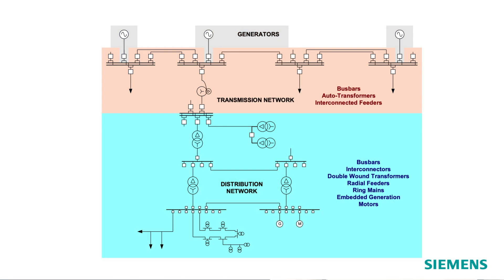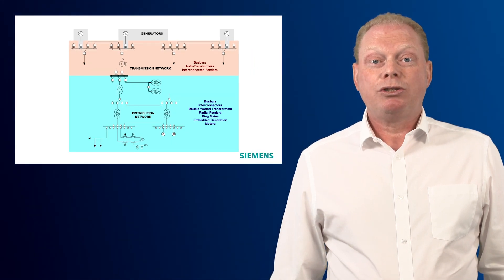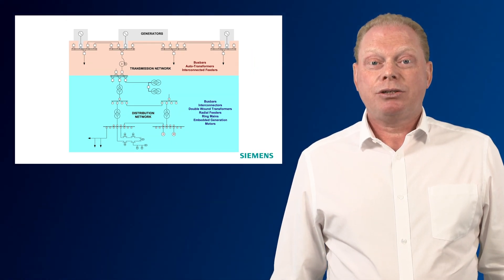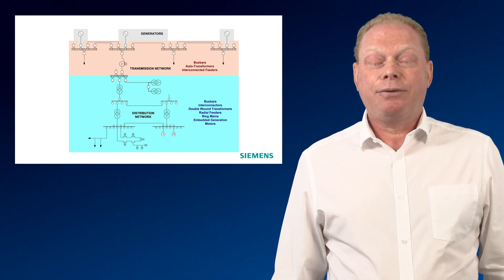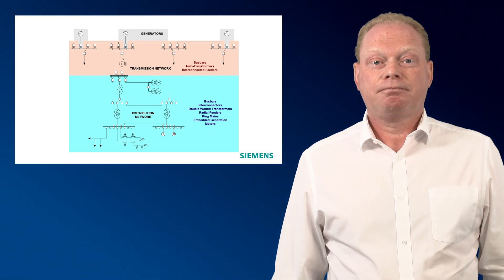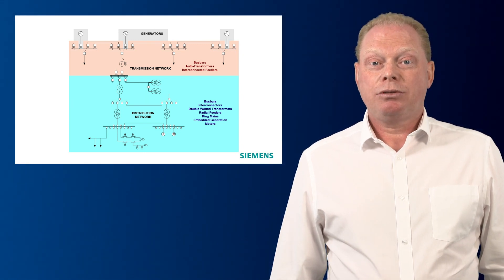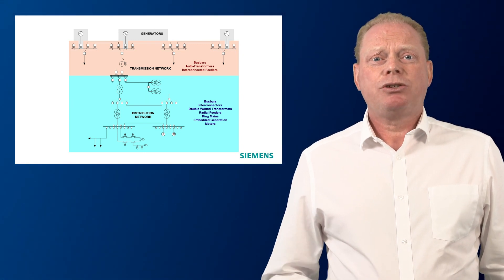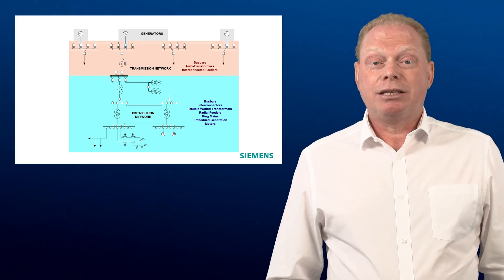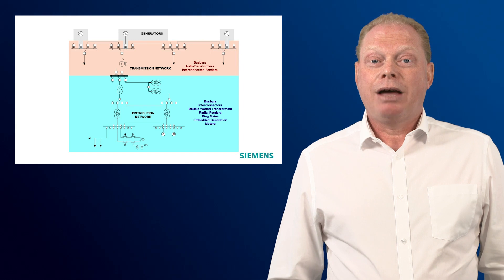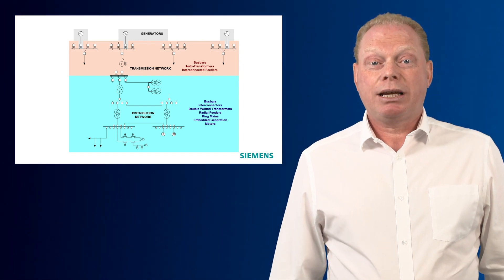For example, system earthing methods and the use of auto-reclose. At medium voltage, ring main systems may be run to increase security and the protection system needs to be able to accommodate these different network arrangements. Also, as more embedded generation is being used, this picture is changing as more generation is being connected at the distribution voltage level, and this also needs to be considered as part of the protection selection.